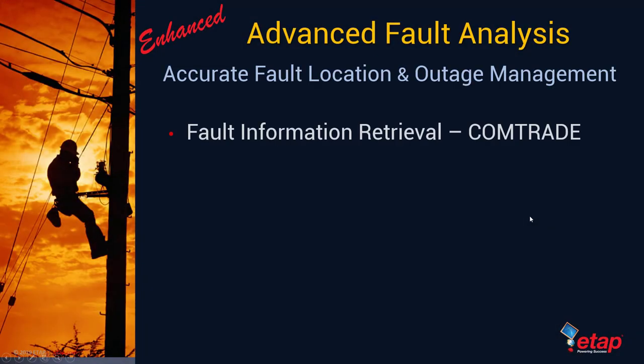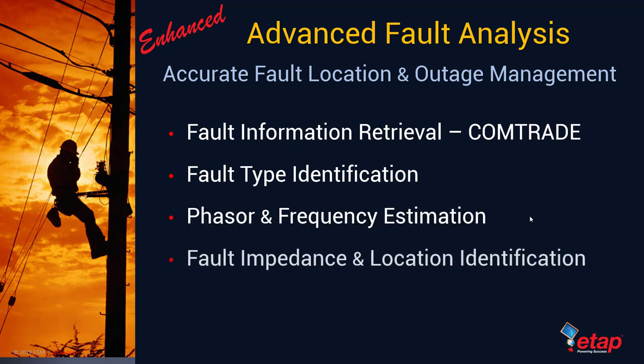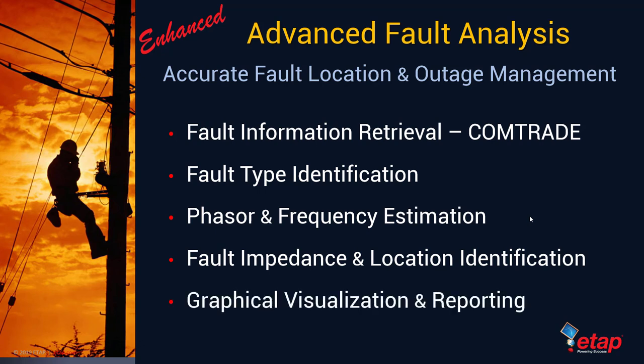AFAS (Advanced Fault Analysis) is also enhanced to allow accurate fault location and outage management integration. Fault information is retrieved from various formats such as COMTRADE, and that information is essentially used to identify the fault type, phasor and frequency estimation, determination of fault impedance and location identification, and finally visualizing the fault impedance and location on the one-line diagram as well as the geospatial diagram, and making that available in terms of outage management and crew dispatch.